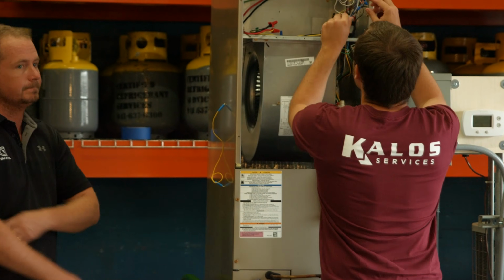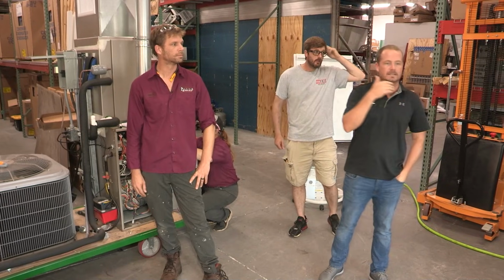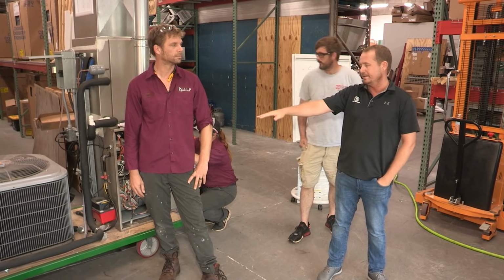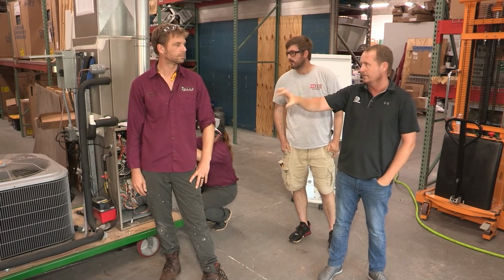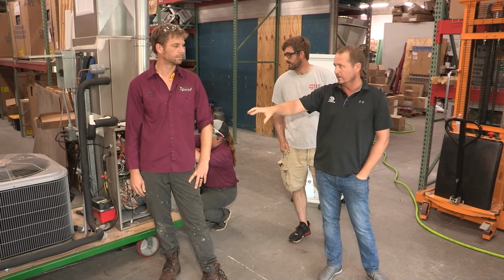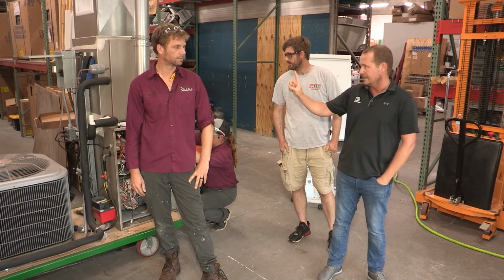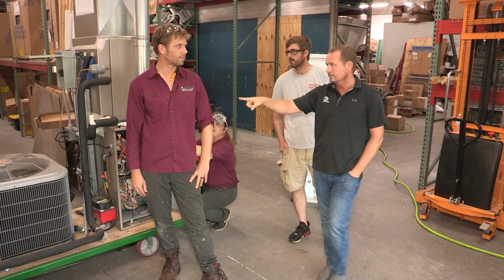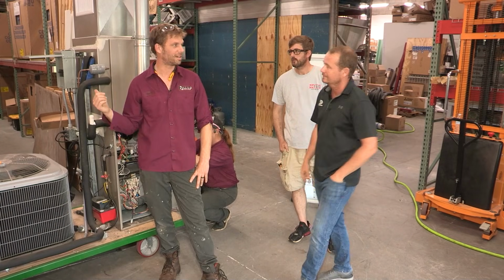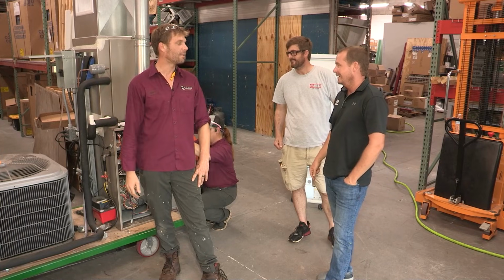The summary of this class is: we've essentially put in a failed contactor, one that we knew had a shorted coil, and it took a little bit to diagnose in this case because main power coming into the unit was off. Yeah, and that was a whole other step.